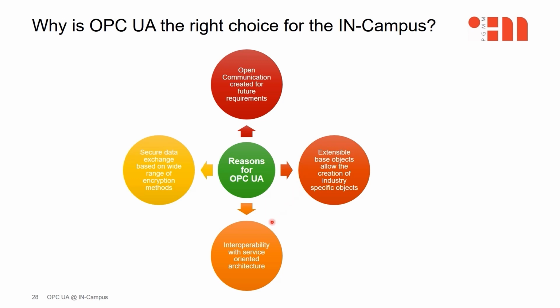OPCUA offers a high degree of interoperability. It is platform and manufacturer independent, has a service-oriented architecture and thus ensures a clearly defined flow of information between devices and systems from different manufacturers. Last but not least, OPCUA offers secure data exchange because it has a wide range of security-relevant encryption and administration methods. It thus offers a high level of protection against espionage, sabotage, and errors. The issue of reliability is also supported by its own redundancy concept to prevent data loss.